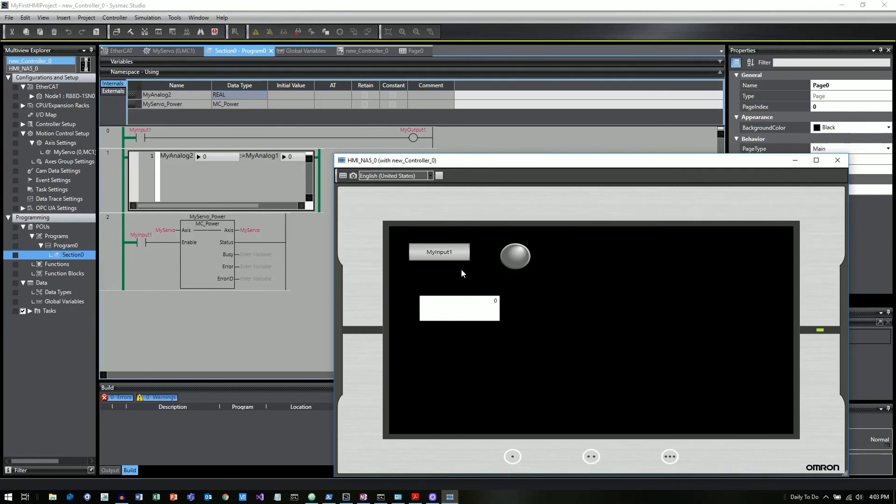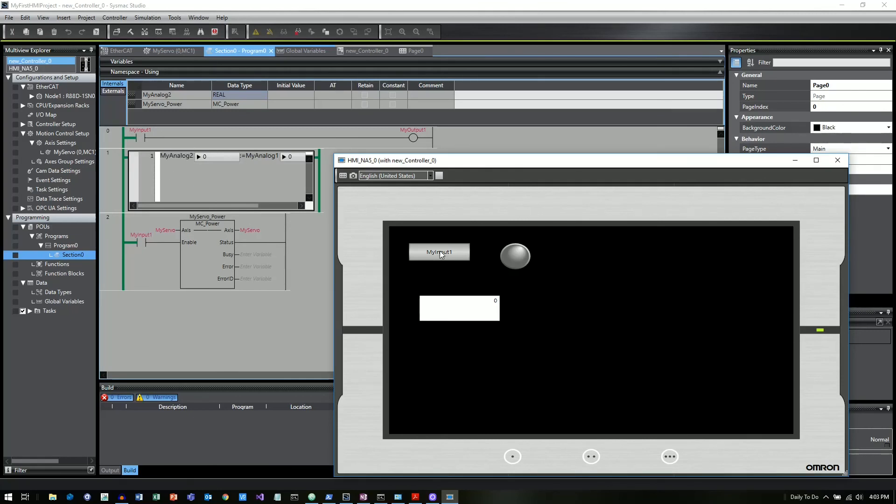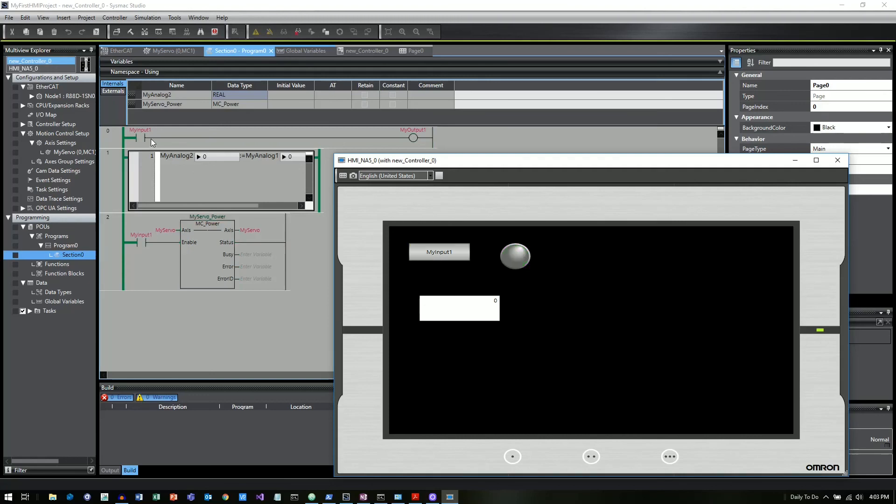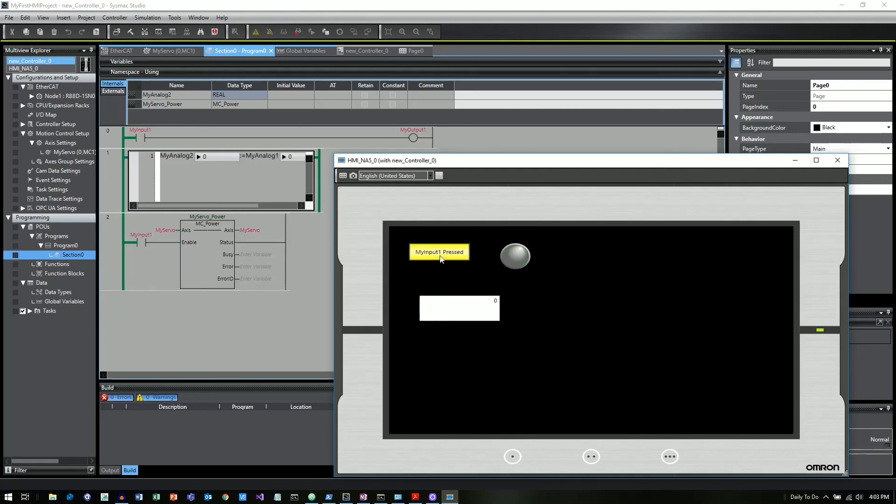So we tied this My Input button to this contact over in the program. So I'm going to mouse over and I'm going to hit that button. And now you can see the text change to My Input 1 pressed. And then if you look up on the ladder rung, when I press that button, that ladder rung goes active. And then the output turns on here. This bit lamp turns on.